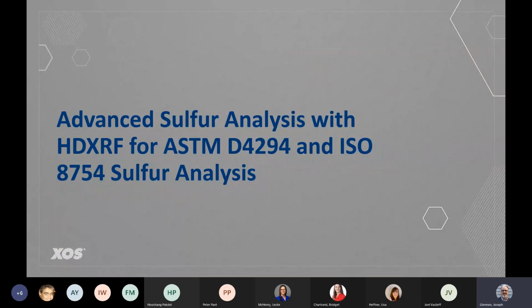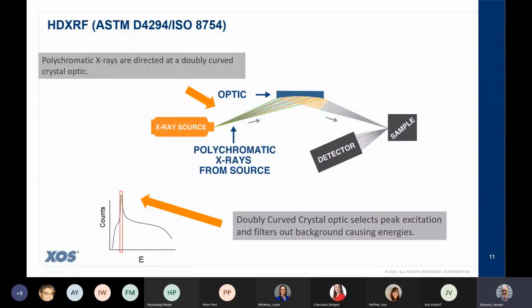Moving on to what we're calling advanced XRF, HDXRF, sorry, which is again what XOS has with the Petra series. In this case, you'll see a slightly different diagram, where the polychromatic X-rays are directed first to a doubly curved crystal optic, which is XOS patented technology. The doubly curved crystal optic selects peak excitation and basically filters out the background-causing energies. So that optic is essentially serving as a filter.